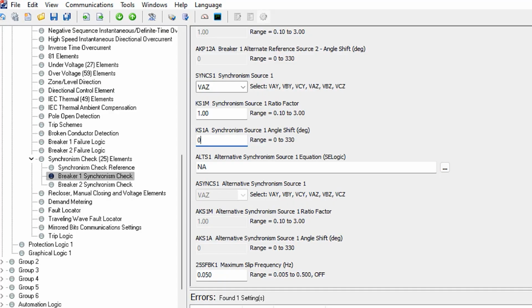So let me go to the blackboard over here. And again, this is a separate example, not for our example, but I just want to show you how you would use this if you had another voltage for your synchronizing voltage. So for example, if instead of using the A phase voltage from the bus side of breaker number 1, we were using the B phase voltage, then we would need to tell the relay, of course, that it needs to compensate for the phase angle difference because it would be comparing A phase from the line side. So let's say that VAY, which is the A phase from the line side, it would be comparing that to the B phase from the bus side. So that would be at minus 120 degrees over here.